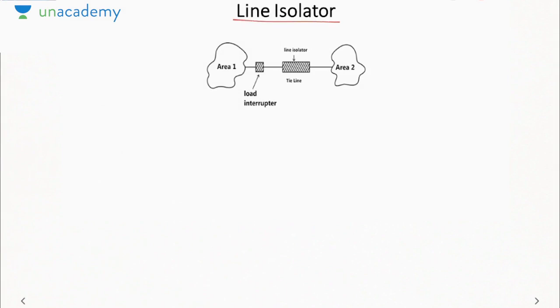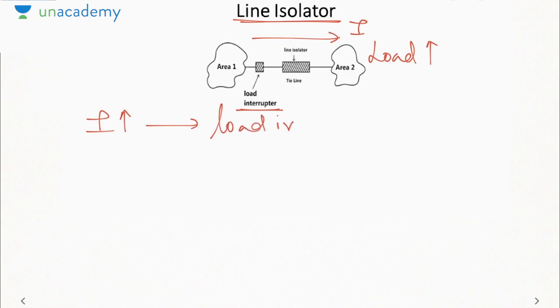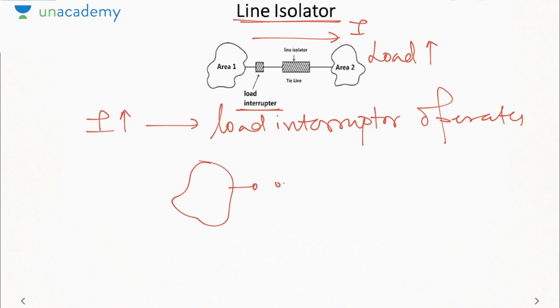Similarly, there is a thing called line isolator. Now as the name suggests, it will isolate the transmission line. It is connected in series with the load interrupter as shown here. Now what will happen is, suppose in area 2 load increases. So here there will be a high current, I will increase. Now what will happen is that this load interrupter operates. If it operates, then what will happen? Then it will disconnect like this.